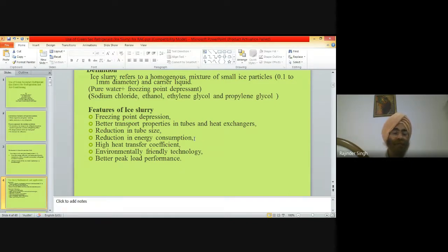Chilled water is a single phase fluid, while ice slurry is a two phase fluid, liquid plus solid crystals. If we use ice slurry, the heat transfer coefficient increases, which is very important. In my design and experiments, I calculated that the heat transfer coefficient increased. As per Newton's law of cooling or heating in convection, heat transfer is directly proportional to the temperature difference multiplied by the heat transfer coefficient. If this coefficient h increases, the Q value increases, so we get a higher heat transfer rate compared to chilled water, and by this we save energy.